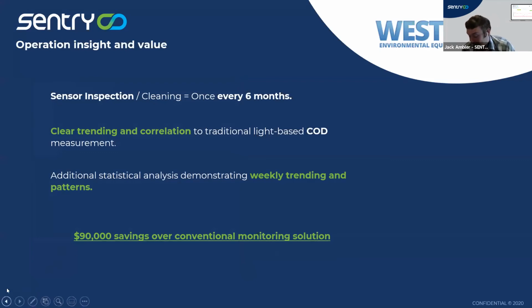Yes, and again, maintenance being crucial for these types of installs. It's been in there for over a year, and it's actually only been maintained one time. So it's just a really important aspect for anything getting inside the collection system. Absolutely fantastic, Jack. Exactly. So having something that doesn't need to be cleaned, or something that is more fit for purpose in a wastewater environment, is certainly more appropriate for those locations where it's just too expensive or too prohibitive to keep going back down there.